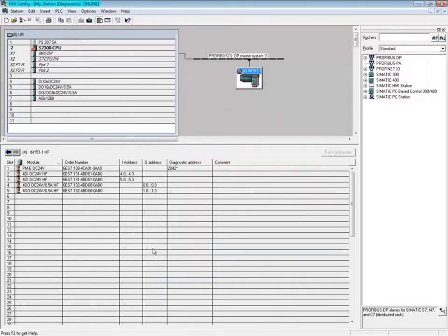We will now do a physical inspection of the system to see if we can determine what's wrong. It could be a PROFIBUS cable, a connector, a failed interface module, no power to the interface module, or something else. After inspection, it was determined that the wires in the PROFIBUS connector to the ET200S station were not making a solid connection. The cable was trimmed, the wire newly stripped with a PROFIBUS cable strip tool, and a new connector put on the cable.